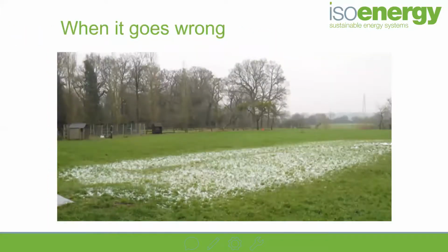And when it all goes wrong, a lot of people, and we'll touch on this at the end with myth busting, are worried about the ground freezing. And again, that is symptomatic of poor design. You should have heat pump systems that have a 20-year lifespan in mind with design. And if they're lasting 20 years, there's no reason why they shouldn't go on to last 50 to 100 years. What we're looking to do in terms of temperatures in the ground is take out about 3 degrees. So that's the delta T, the difference between our outgoing brine temperature going out into the collector and the incoming. We're looking to harvest 3 degrees from the ground.